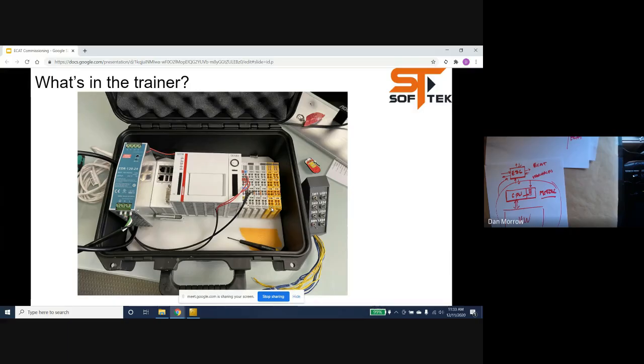And then the other piece of it is they're very concerned about people cheating with safety. So there are additional safeguards, including dip switches on the sides of these modules, so that these modules are addressed. There's a set of dip switches on these things.